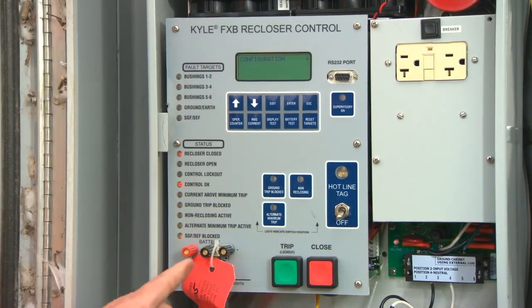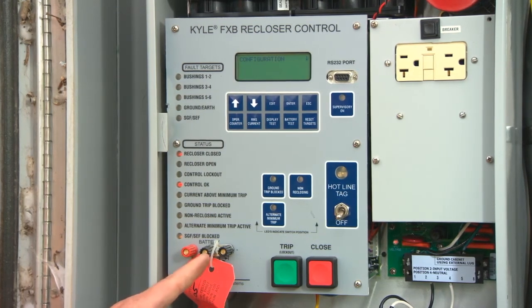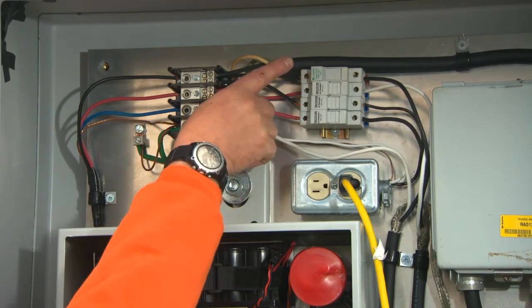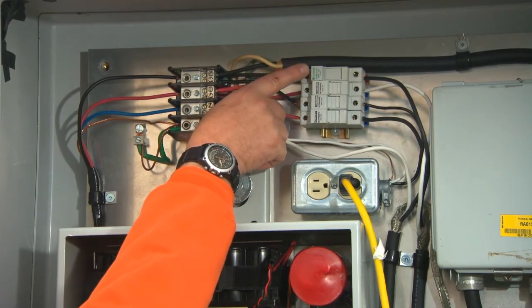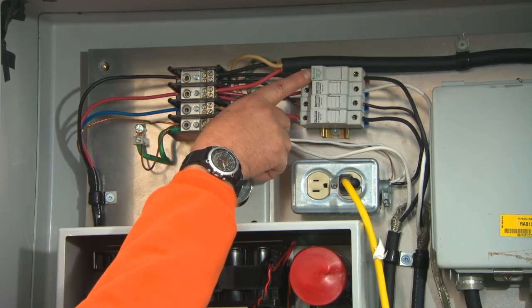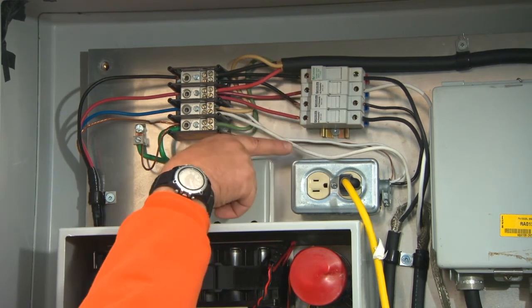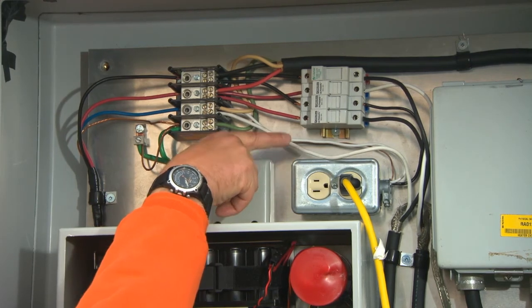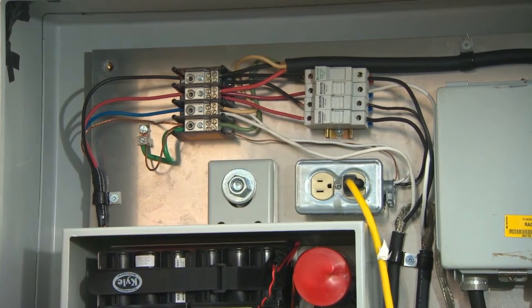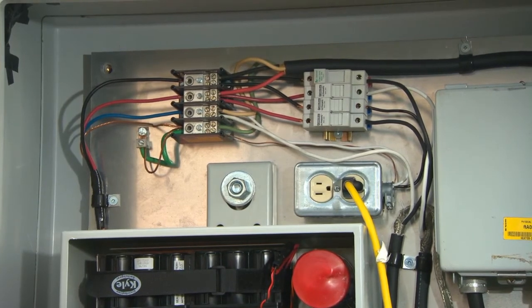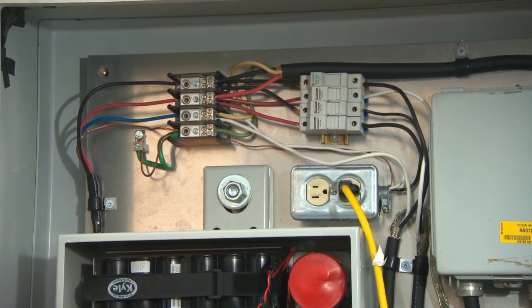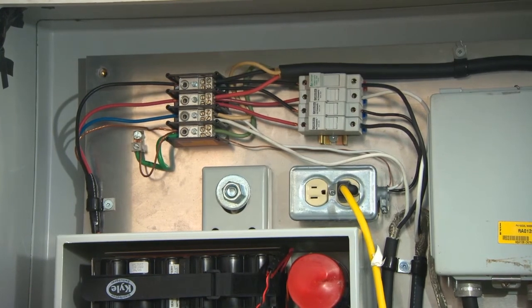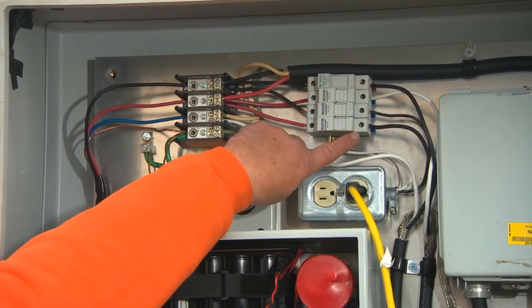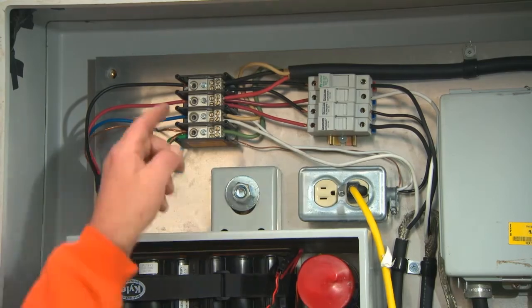On the bottom of the unit are the battery test terminals. Applying a voltmeter to these will display the current floating voltage state of the battery. Across the top of the control cabinet are fuses. These fuses are for the control panel, the receptacle inside the control panel, along with the 240-volt supply for the closing coil. Should a problem occur with this unit, such as a lack of AC power or a recloser refusing to close, please verify that from the fuse to the ground you have 120 volts.